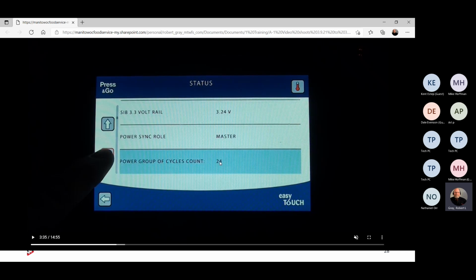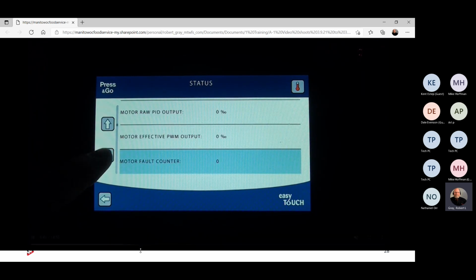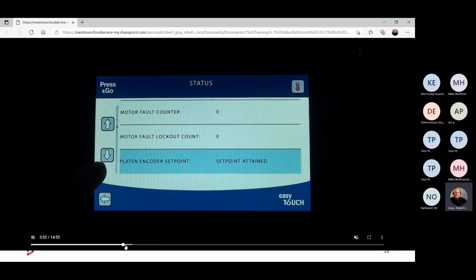And the group cycle count. You have 24 available cycles. We only use 15 cycles of the 24. So during your power calibration, we get up at 1 or down at 1, etc. I'll show you that as well when we get to the calibrations. And then other information that's under here. There's a lot of stuff in here that tells you other things, but we don't need to go through all that in the training. None of that is really going to help us out there in the field. But if you want to look at it, take a look at the video and you can see everything that's under there.